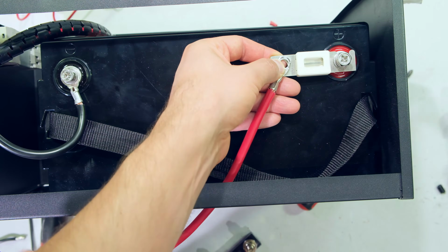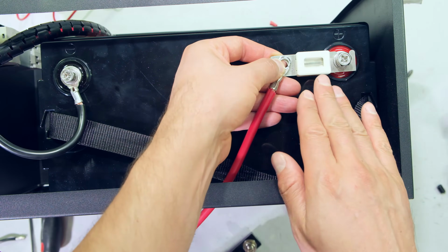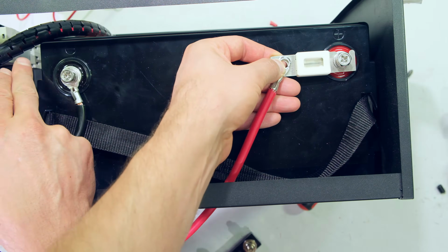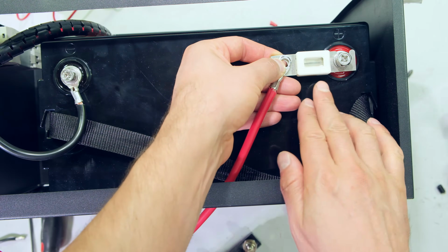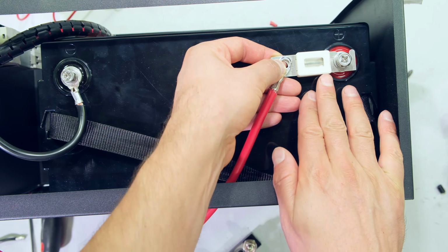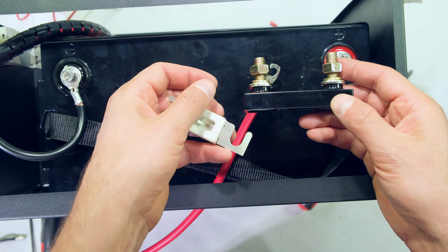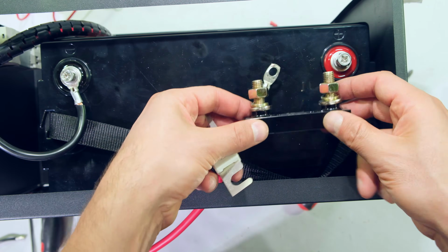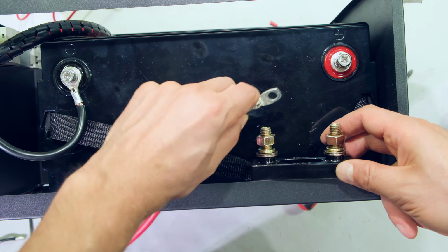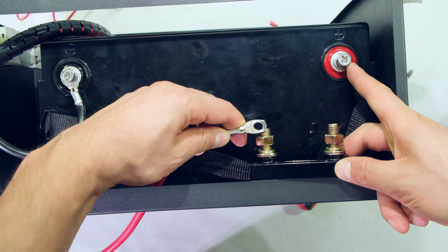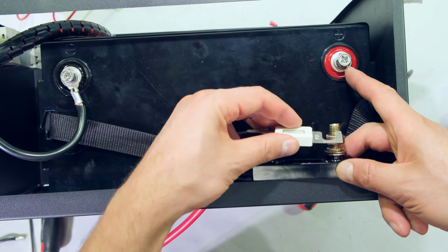If I'm using a fuse and a circuit breaker, then this fuse has to be rated higher than the circuit breaker. So the circuit breaker is 50 amps, which means this fuse should be 60 amps, or even a bit higher, can be 70 amps. It's best practice to put the fuse on a fuse holder. This could be mounted on the chassis here, and then we'd have the one lead over there, and then just a fly lead going to there, and the fuse sits here in the middle.